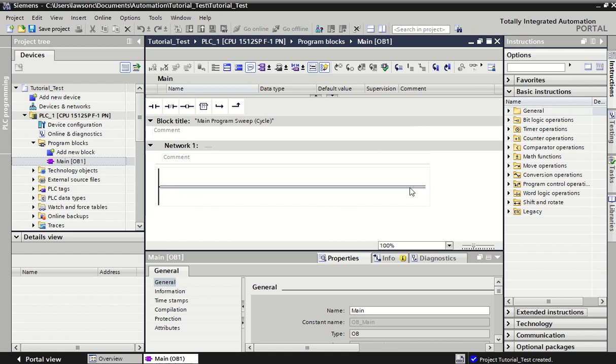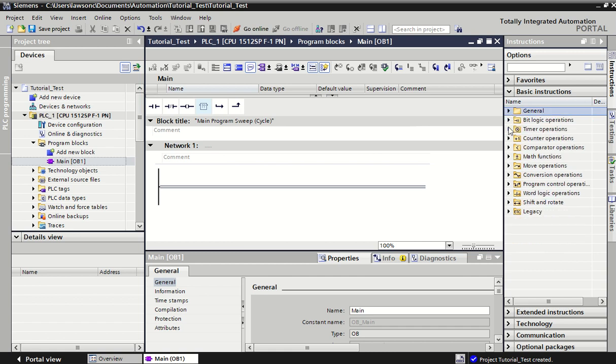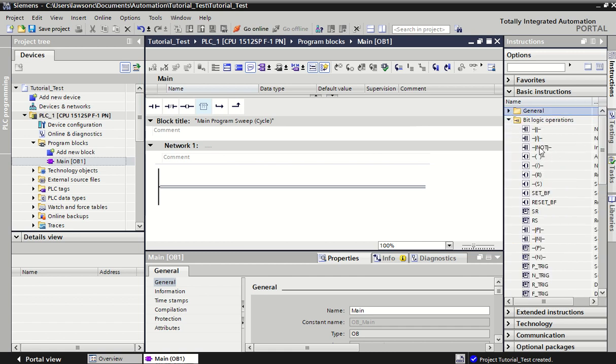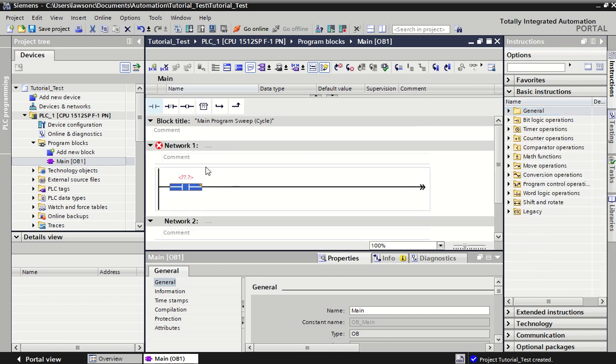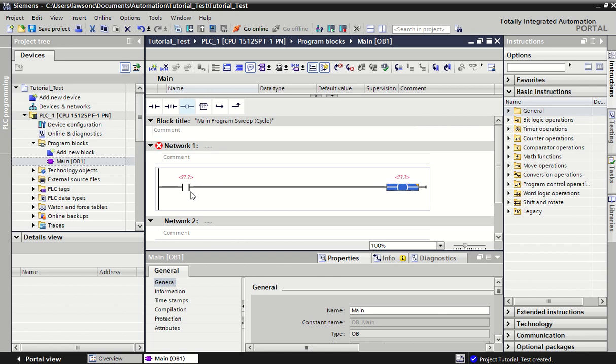Within ladder logic, we have a piece of code per rung on the ladder. This is like a rung on a ladder and we're always trying to get energy flowing from the left over to the right. Within each rung we'll usually be controlling one output and making decisions based on certain inputs to turn on that output. Our input symbol is this normally open contact here, and our output symbol is this one. You'll find them under the bit logic operations — normally open, normally closed, and coils for outputs.